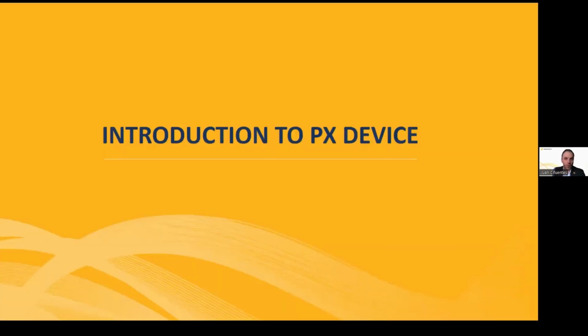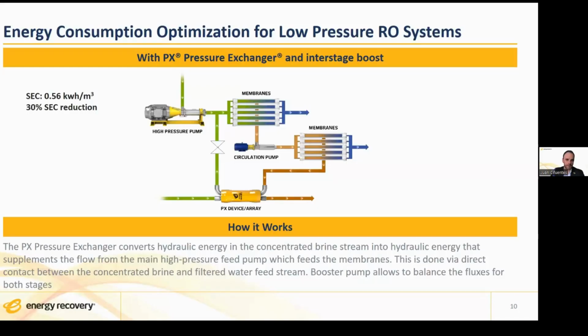Let's see what the PX pressure exchanger is and how it works. We can modify a low pressure two-stage system from the normal design of a high pressure pump and 2 stages. We can introduce an interstage circulation pump and the PX to reduce the specific energy consumption up to 30% or lower, as low as 0.56 kilowatt hour per cubic meter.